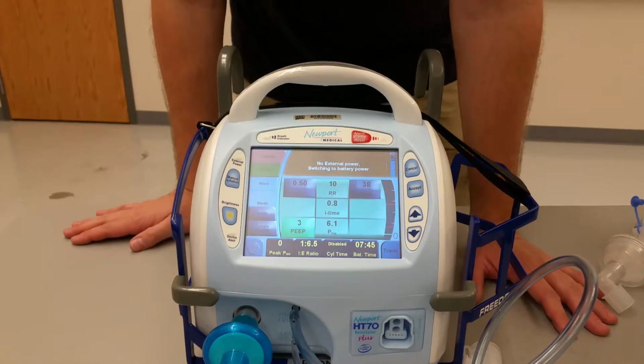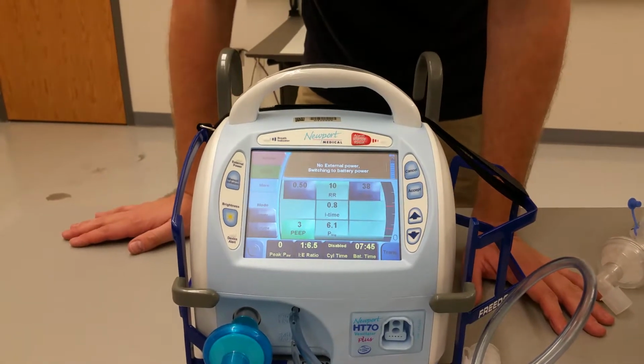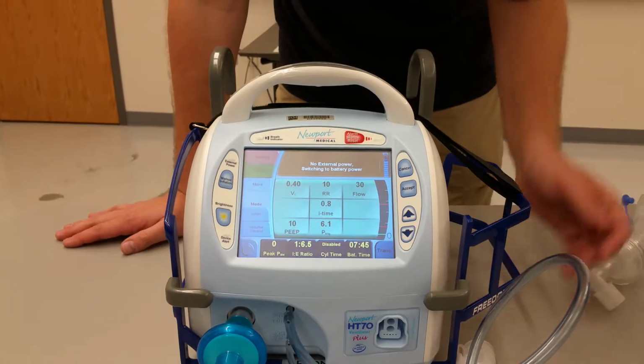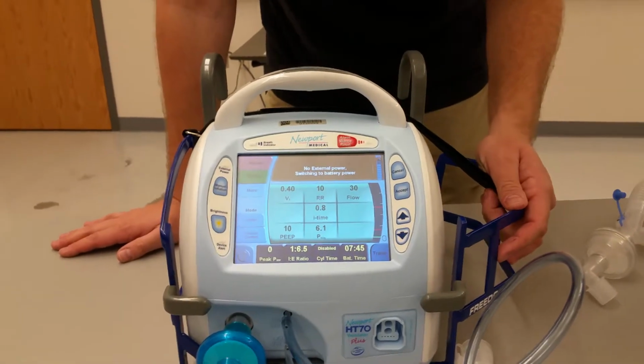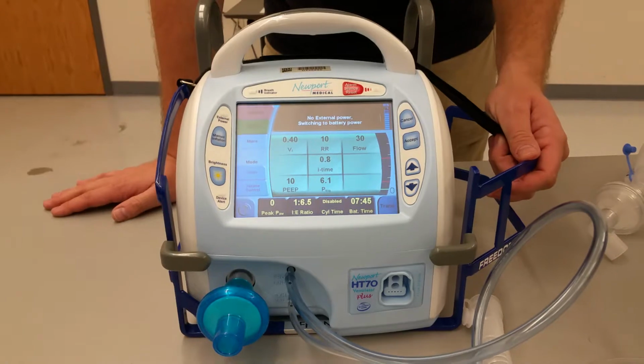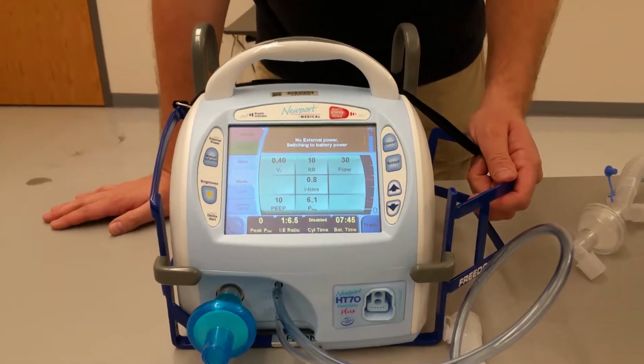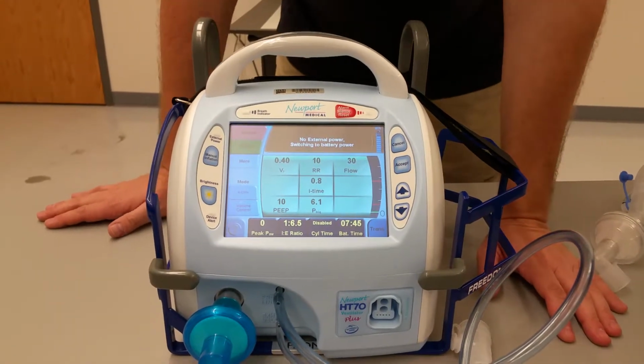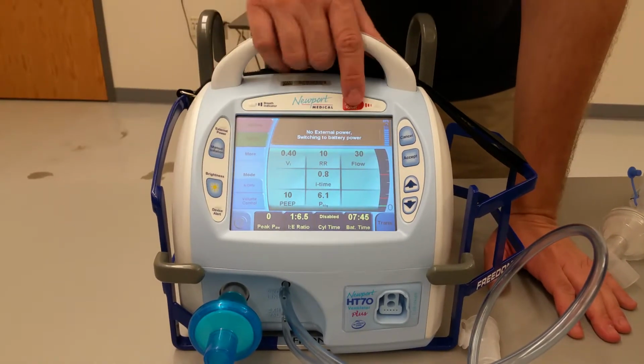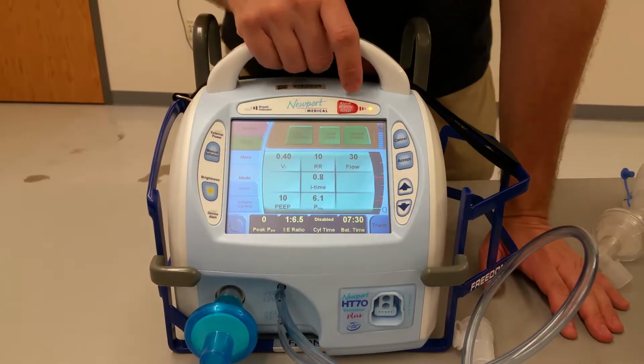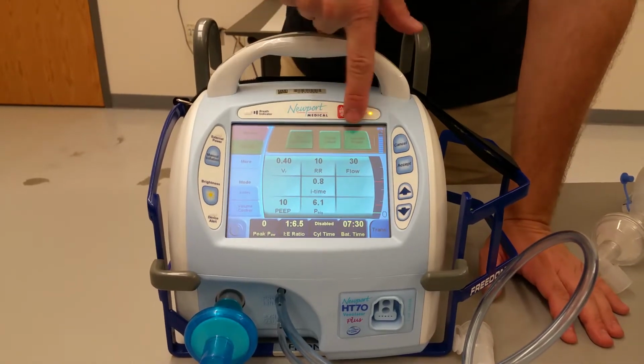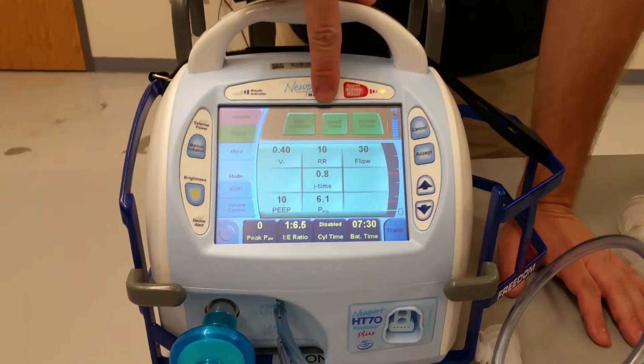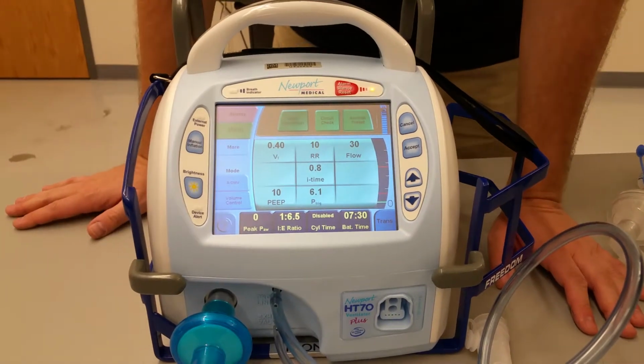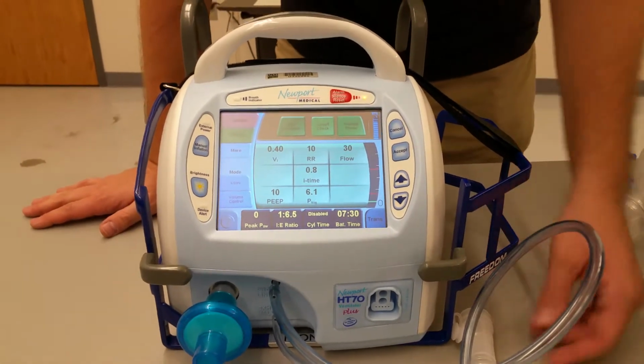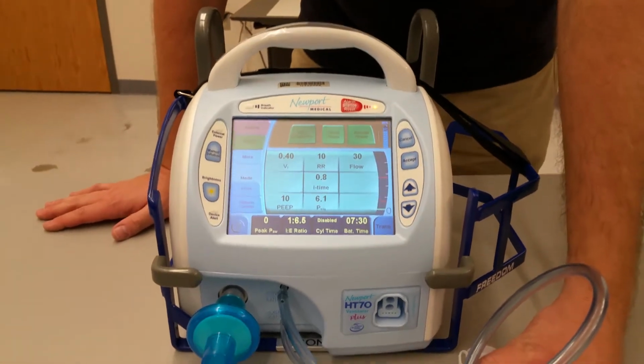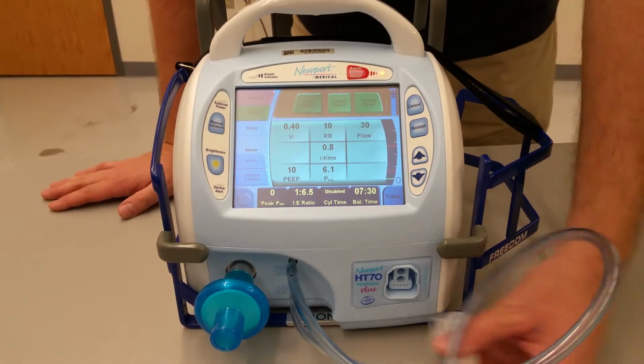Okay. I time, does that look like a good I time? Inspiration, what is it? Yeah, 0.8 seconds. Yeah, that's pretty fine. About right. You guys okay with that? 0.8 seconds to inhale. Okay, so now once I've got all my settings in, we'll go ahead and clear our alarms out. And once I've cleared all my alarms out, you see at the very top here, I have start ventilation, circuit check, and activate presets. We would actually do a circuit check, but we're just going to defer that for now.